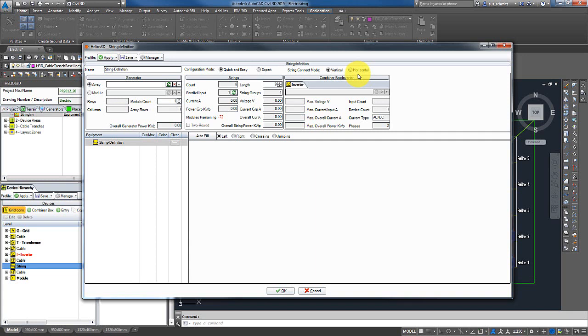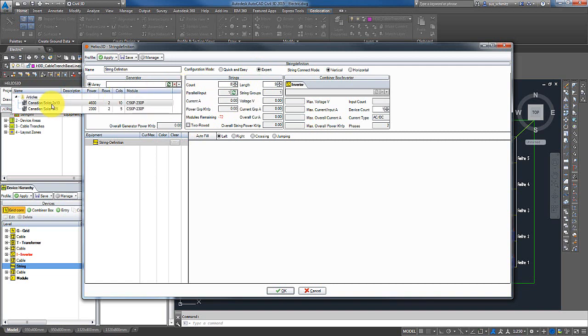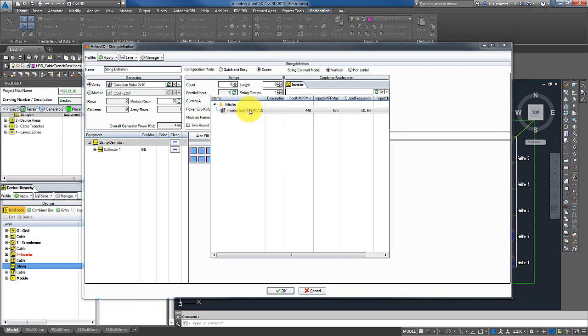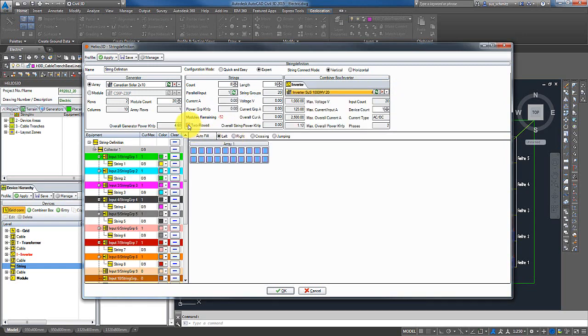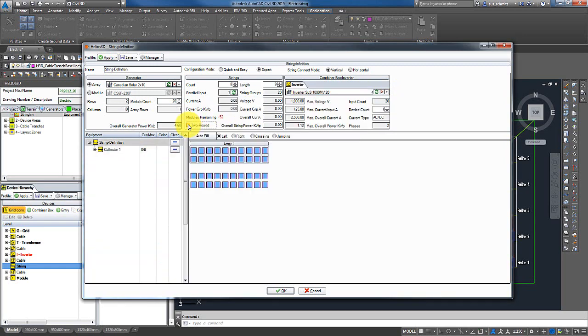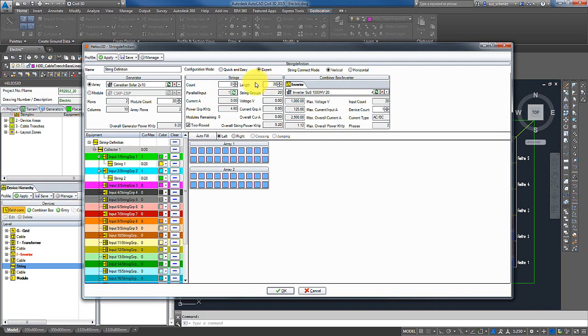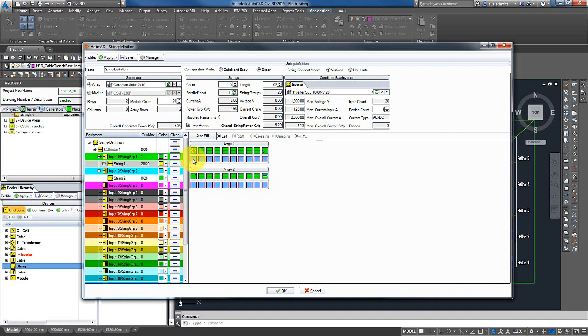Another option we added is the option two row strings. For that, we have to enable the expert mode. When I now select a table definition and an inverter, I can enable this option for creating a layout above two tables in different rows. Now I can set the number of strings to 2 and the length I keep at 20, and I can now create my layout like this.